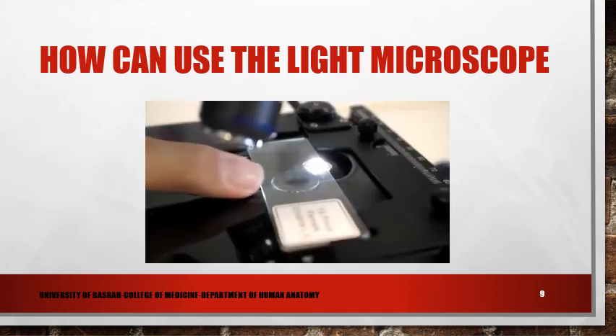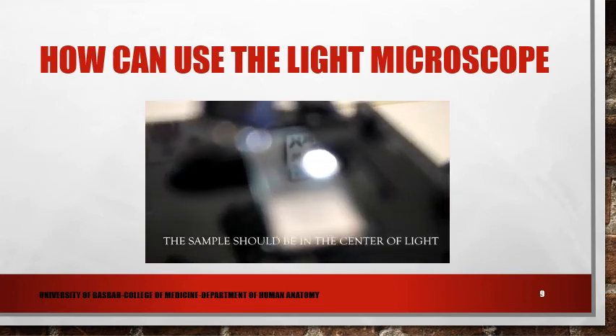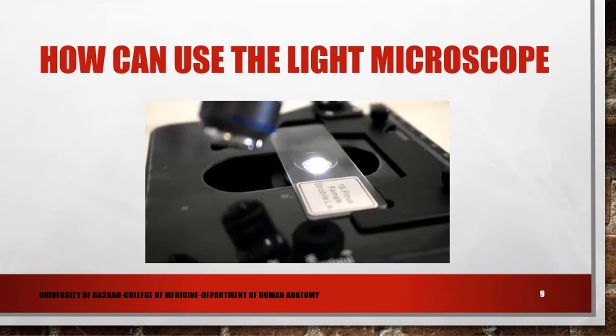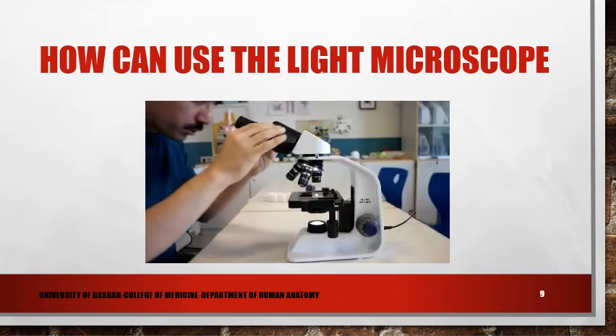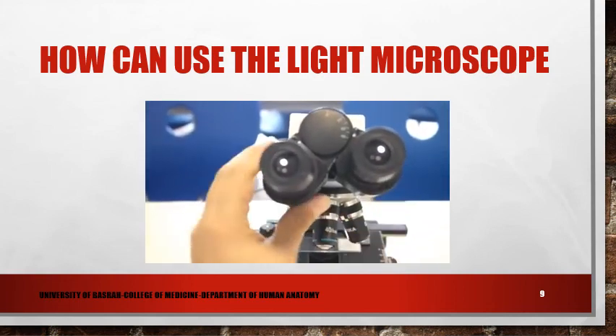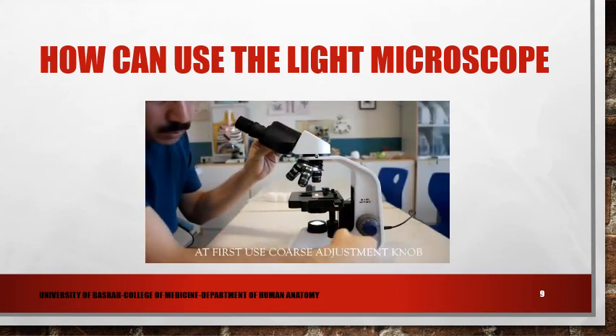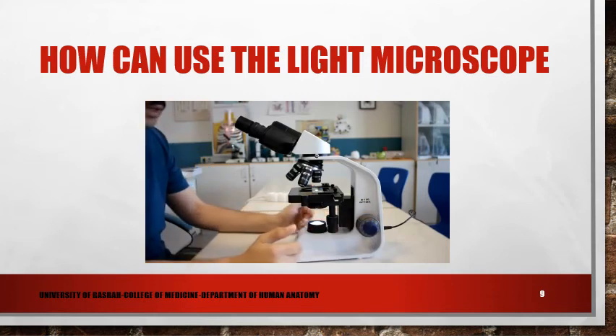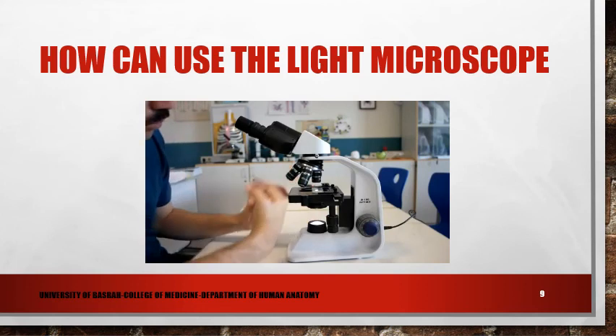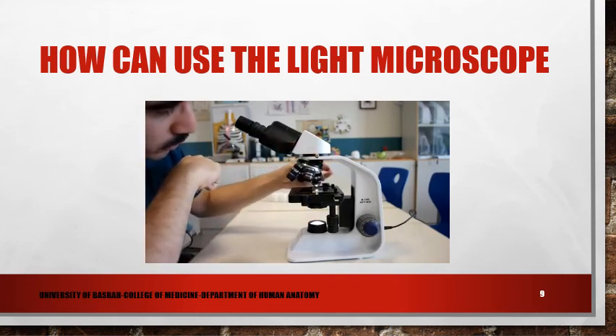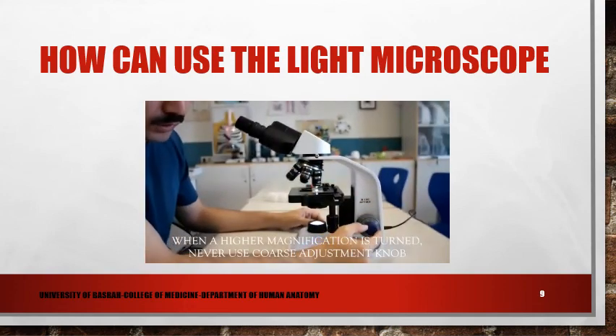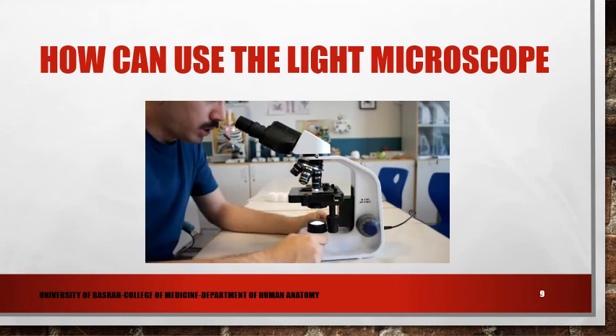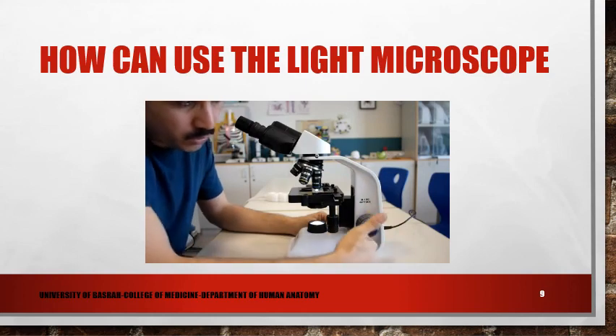Make sure the sample is right in the center of light before you start looking through the eyepiece lens. You can adjust the length according to your eye. Use the coarse adjustment knob only to move the stage up. When you need to turn to a higher magnification, rotate and use only the fine adjustment knob, never use the coarse adjustment knob anymore.